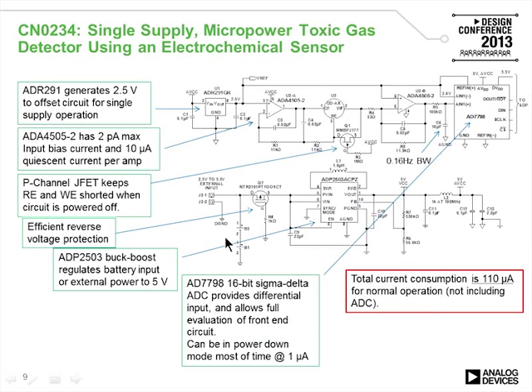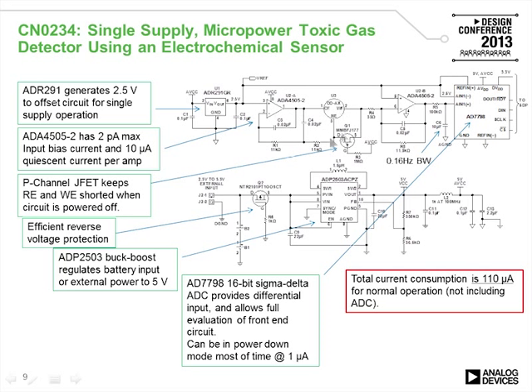This is the basic schematic of the reference design for the gas sensor. In the center we see the sensor itself. The transimpedance amplifier — the ADA4505 dual — converts the current into voltage. A FET is included to prevent damage to the sensor on startup. This is the input buffer, and this is the feedback path which forces the counter electrode to the correct voltage so that the voltage across the working electrode and reference electrode is zero.